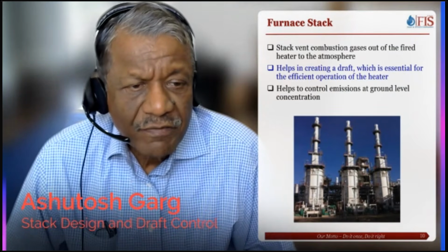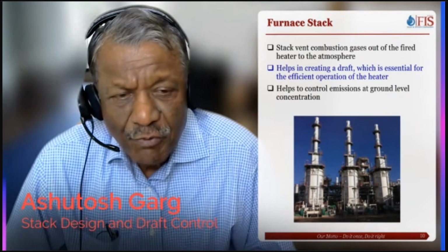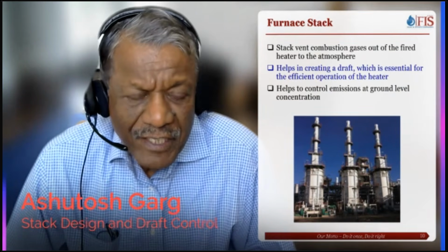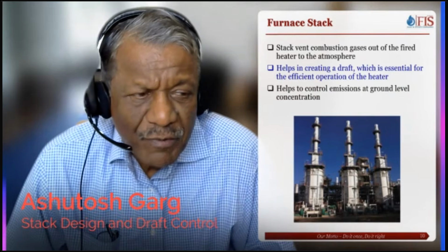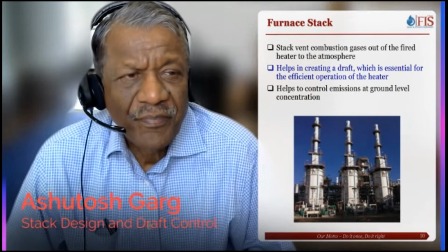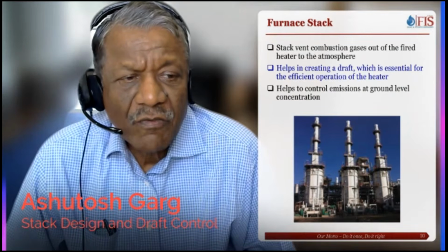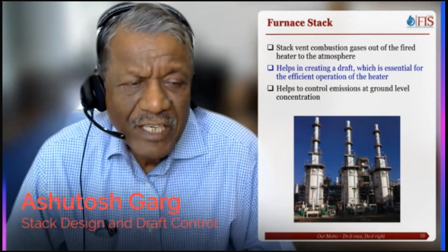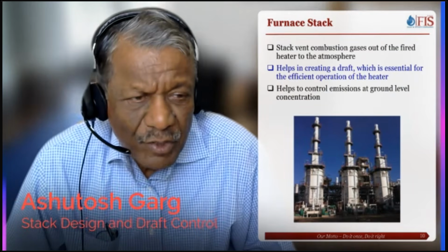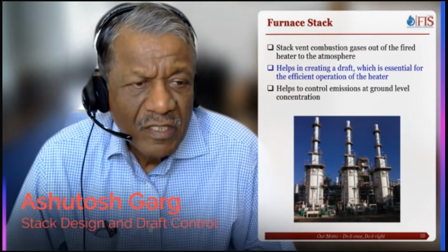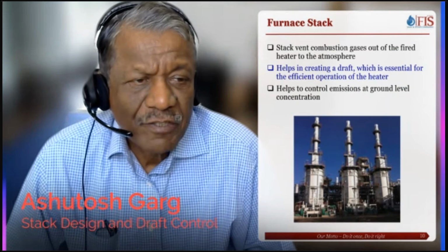But fired heaters are process equipment, and being process equipment, we want them to be inherently safe. Because of that, we want to make sure that anytime anybody opens any peep door, the flue gases should not come out.